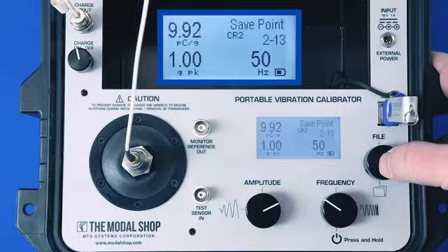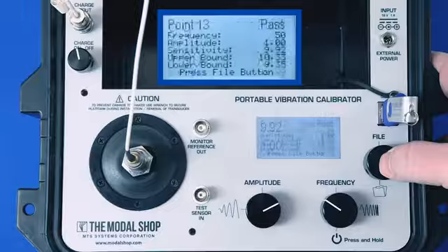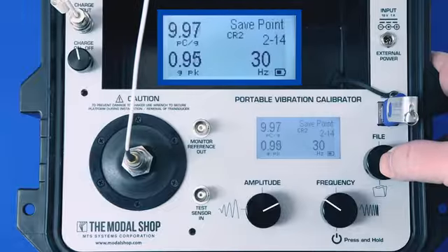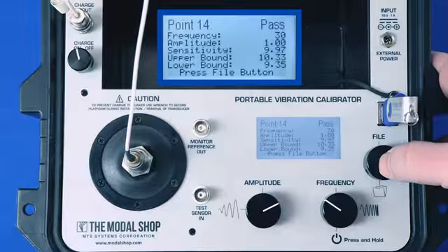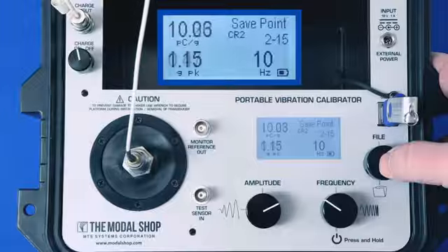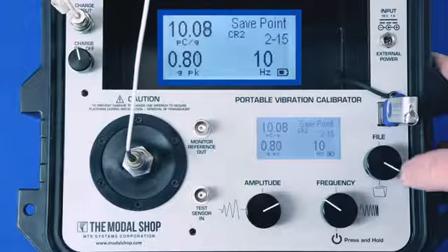So if you want to test a 10% band, you can go ahead and do that, and the pass-fail will be calculated based on plus or minus 10%. And again, we have another video available to show you how I programmed, specifically how I programmed this test. 30 Hertz is a pass, and this is our last test point at 10 Hertz.